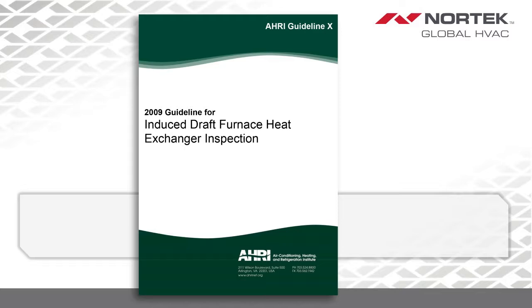Okay, great. Thank you. Moving on to our second method, which will most commonly be referenced by the guys in tech service when they're talking to mechanics out in the field. That method uses the procedures laid out in the 2009 AHRI document. It's an 8-page document for inspection of the heat exchanger on an induced draft forced air gas furnace.